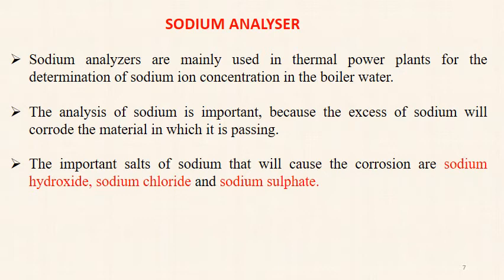Sodium analyzers are mainly used in thermal power plants for the determination of sodium ion concentration in the boiler water. This analysis is also helpful for the detection of leakage in the condenser. The leakage can be detected by measuring the concentration of sodium in steam and in the condensate. If the two measurements give different values of sodium concentration, then that indicates the leakage in the condenser.